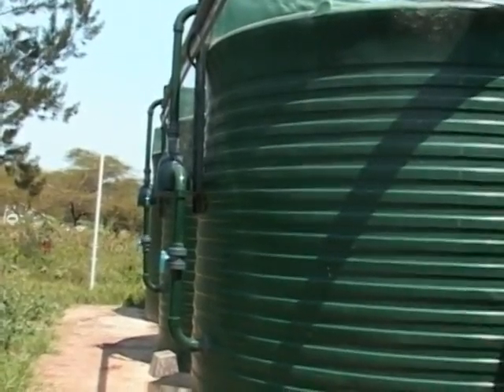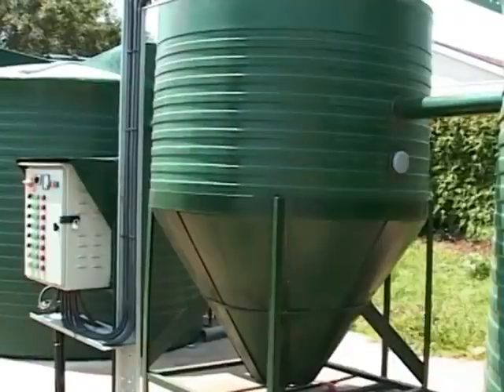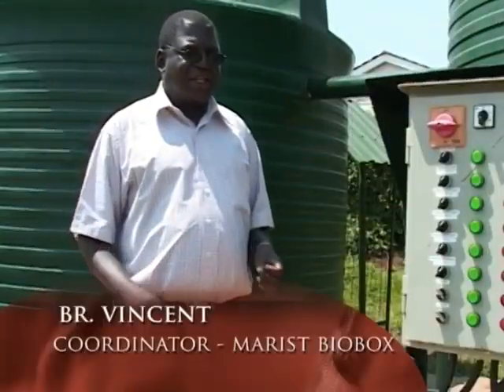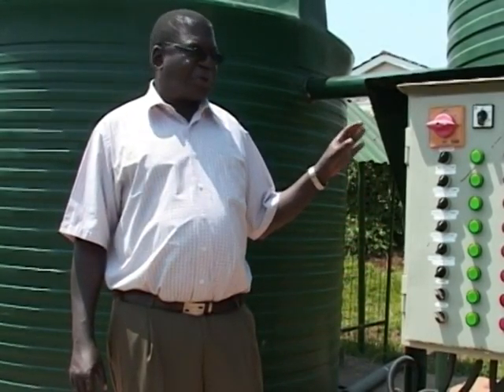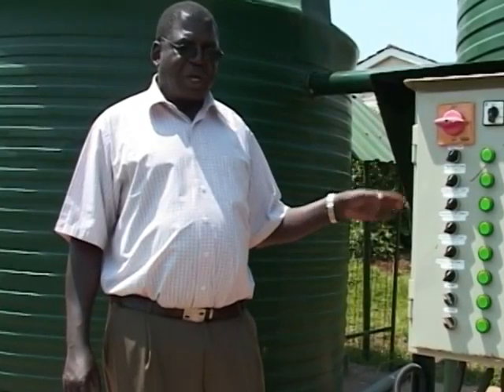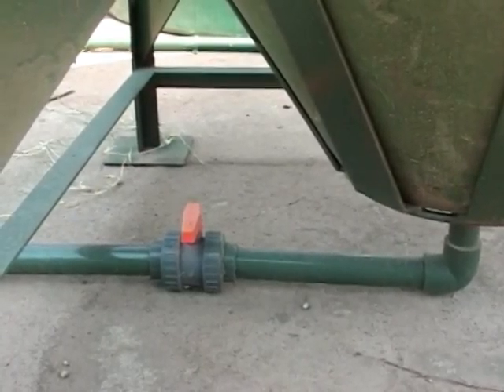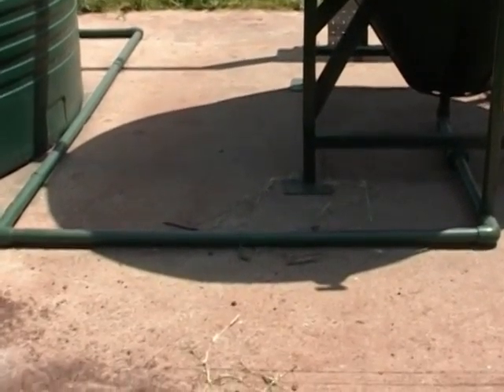After the third tank, it goes to the smaller tank. This smaller tank is conical shaped. The idea is that if there is anything still solid in the water, that particle will settle at the bottom of the tank. Then once a week, we open the outlet of this tank and anything solid goes back to the septic tank, where it gets digested again.